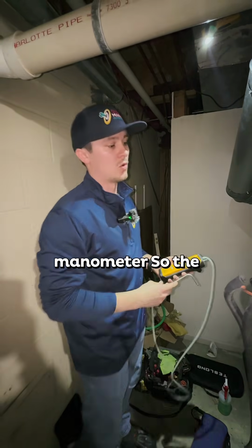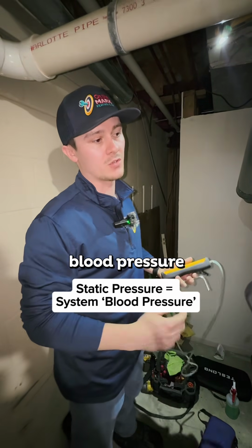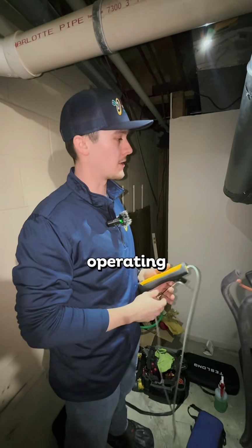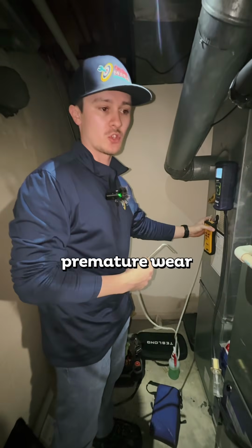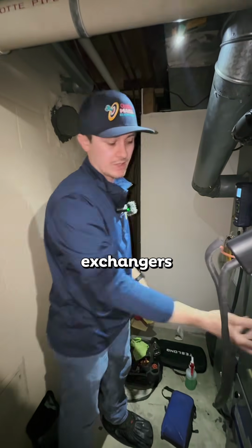This is called a manometer. So the static pressure in the system, it's kind of like blood pressure. It tells us a lot on how the system's operating. High static pressure can lead to things like premature wear, premature failures on things like heat exchangers, blower motors. We're going to check static pressure and temperature there.